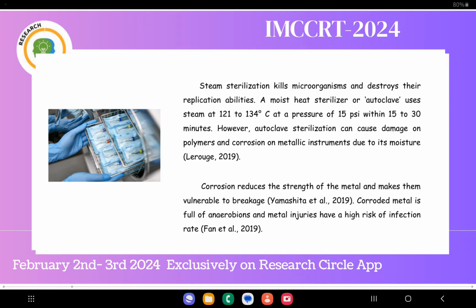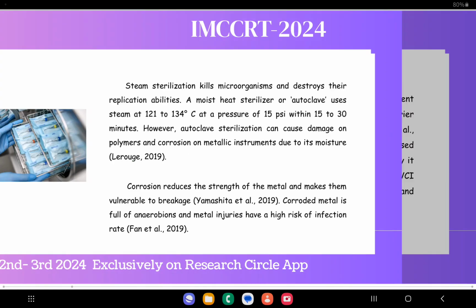Steam sterilization kills microorganisms and destroys their replication abilities. A moist heat sterilizer or autoclave uses steam at 121 to 134 degrees Celsius at a pressure of 15 psi within 15 to 30 minutes. However, autoclave sterilization can cause damage on polymers and corrosion on metallic instruments due to its moisture. Corrosion reduces the strength of the metal and makes them vulnerable to breakage. Corroded metal is full of anaerobes, and metal injuries have a high risk of infection rate.